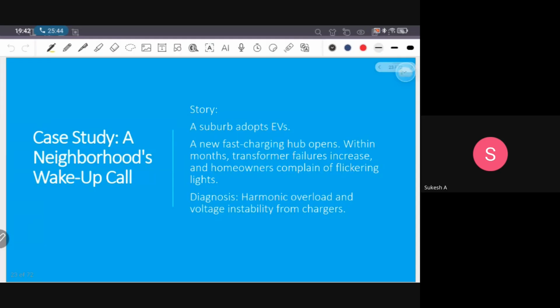So there was a case study. This narrative makes the problem real. A suburban neighborhood embraces EVs. A developer installs a fast charging hub anticipating demand. Within months, the local utility transformer begins failing repeatedly. Homeowners complain of lights flickering and electronics behaving oddly. An investigation reveals the root cause: the chargers are generating harmonic currents that overload the transformer and create voltage instability.